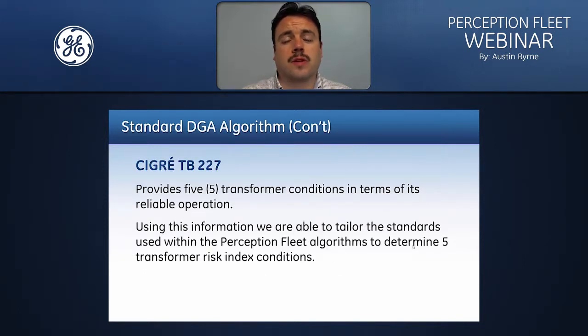Another thing that we've done with our DGA algorithm, as well as looking at the IEEE and IEC standards, is we have taken in some CIGRE TB 227 best practice techniques. The technical bulletin TB 227 provides 5 transformer conditions in terms of reliable operation. And what we've done is we've taken these best practice techniques and applied them into our algorithms to add more in-depth evaluation of the asset.